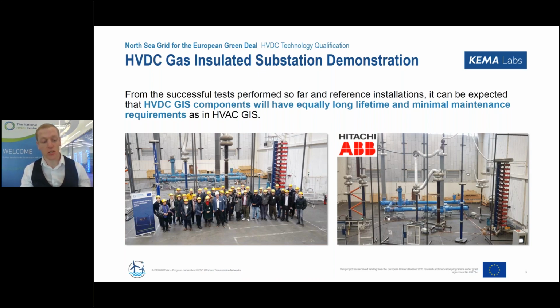The testing was done as part of Work Package 15. Up to the present time, there are no international standards describing the requirements, applicable tests and test procedures for HVDC GIS that have so far been developed. Within Promotion, focus was given to the dielectric test requirements due to the different nature of DC electric fields compared to AC fields. Additionally, due to the lack of operational experience on HVDC GIS, there was demand from utilities and regulators for long-term testing to prove the dielectric performance of the prototype installation under actual service conditions.